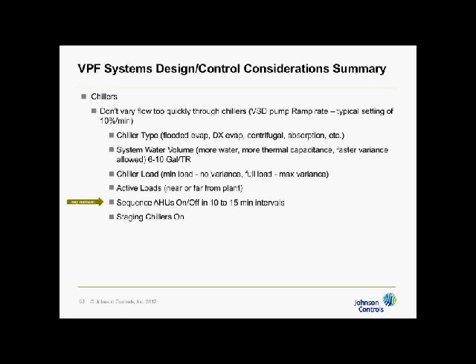Right? There's another thing that has nothing directly to do with the chiller, but remember, with a VPF system, I'm no longer isolated from what happens at the air handling units. When I'm in primary-secondary, I'm hydraulically decoupled from what's going on out there in the secondary, from flow and head changes as I change valves and so on. But no longer am I. And that means that you don't want to shut a bunch of air units off at once and close their valves, because you'll get a sudden change in flow, and that will trip the chillers off. So sequence the air handlers on and off in 10 to 15 minute intervals, so you don't have that problem.